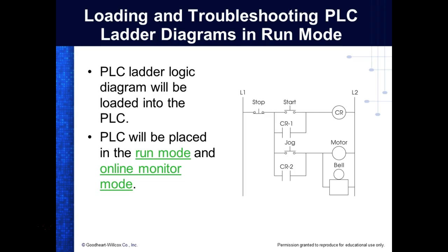So that's a really good troubleshooting tool, guys. If you're expecting an input, instead of you going out to the line anymore, if you got your PLCs on a network, and we can network these, especially this, because this is Ethernet. So I could literally hook this up to my plant network, and if I'm having problems, I could go online and see that sensor working or not working, right? Y'all understand that? I can see if it's false or true right there.